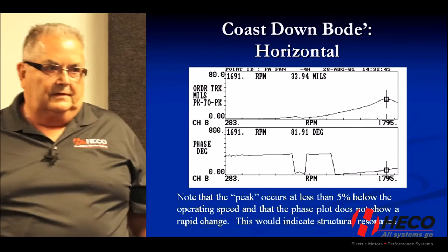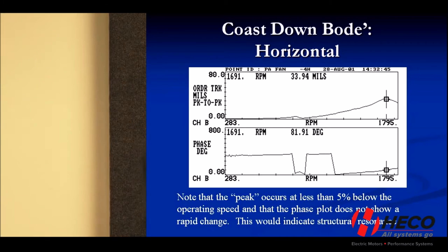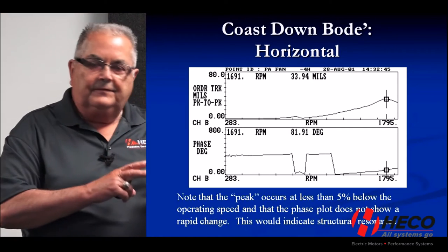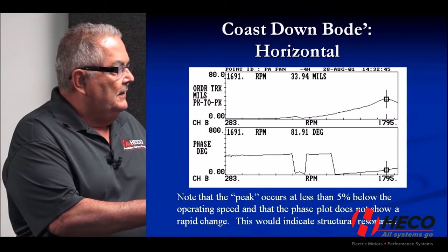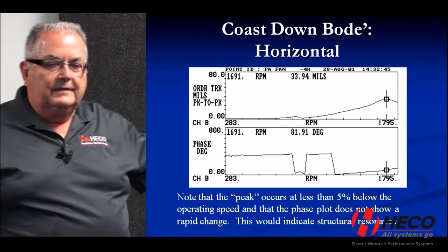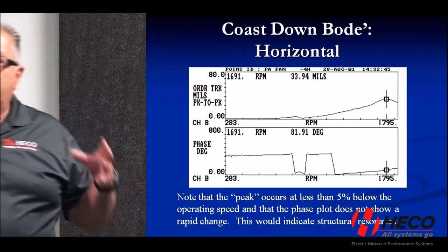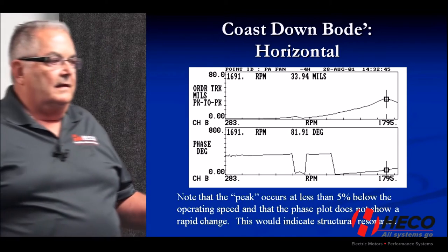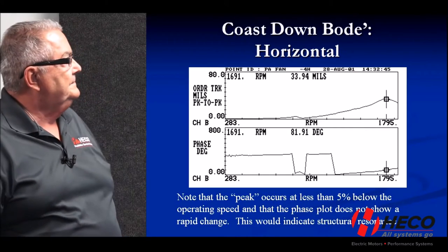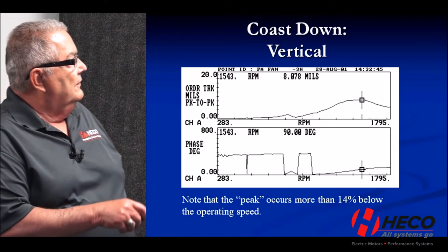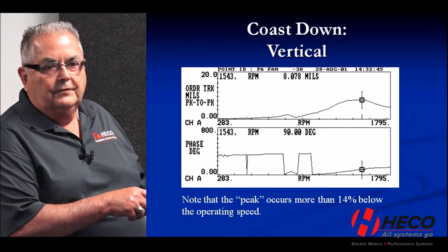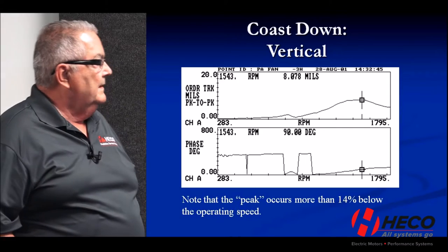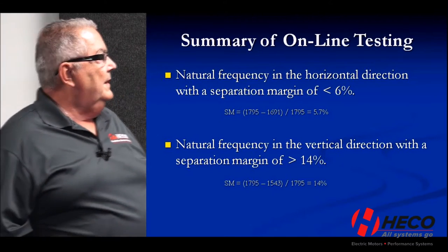That peak indicated we were passing through a natural frequency or resonance condition. Looking at the phase angle, it was not changing very rapidly. If it were a natural frequency of the fan wheel or shaft, you'd expect close to a 90-degree phase change happening rapidly. The combination told me we have a resonance, but it's not resonance of the rotating assembly — it's structural. Something in the foundation or structure of this fan has a natural frequency where there shouldn't be one by design.